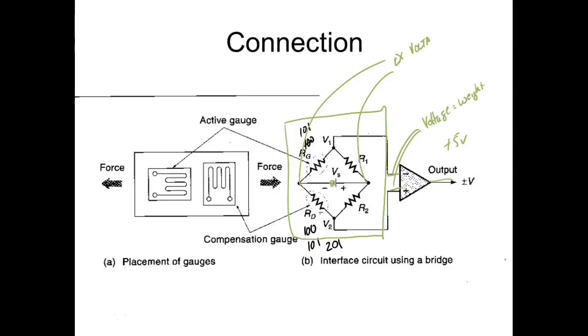So what you're doing is you're establishing what zero is, right? That's what we would do when we changed the load cell out. We would reset. We would come in and put zero weight on there, and we'd zero the scale. Then we'd put calibrated weights on there. They had to be checked every year. We had to haul them down to Montgomery, and they had to make sure they were calibrated according to a standard, especially if you buy and sell off your scales.